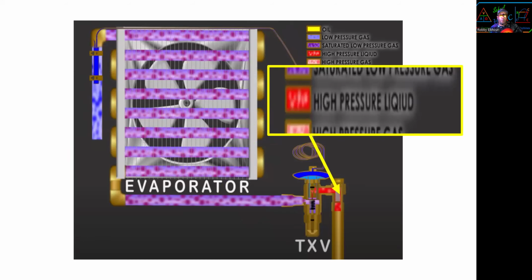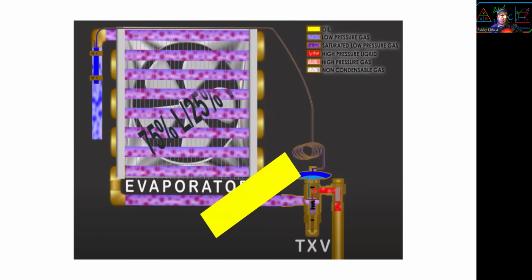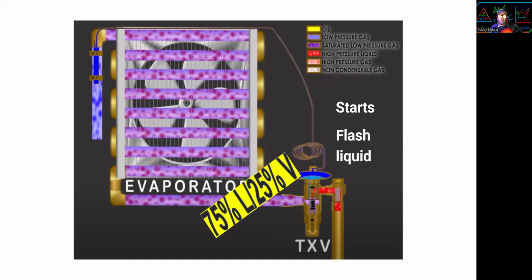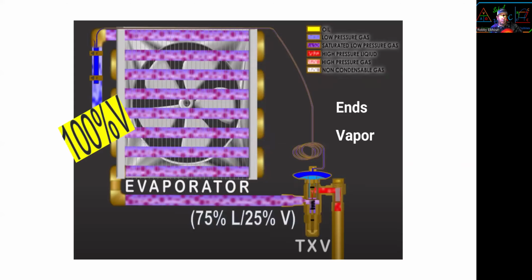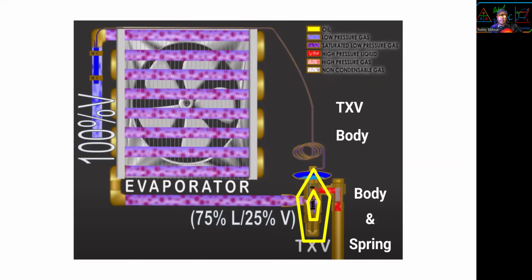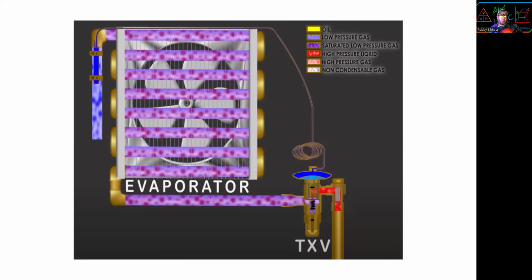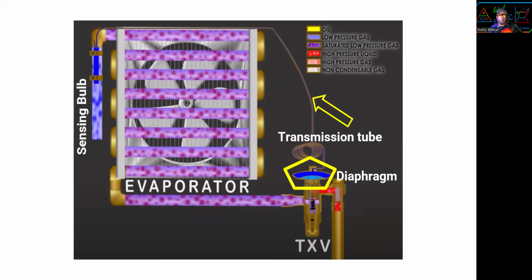Okay, and high pressure liquid enters the metering device. 75% liquid vapor mix, or 75-25. Freon starts to flash liquid, ends 100% vapor. The TXV is made out of the body, and the spring is inside. And we have the diaphragm, also called head. And the diaphragm, transmission tube, and the sensing bulb. That's part of the head. So the head is the diaphragm, transmission tube, and the sensing bulb. There's your sensing bulb right there.